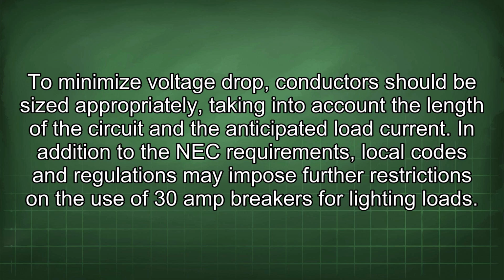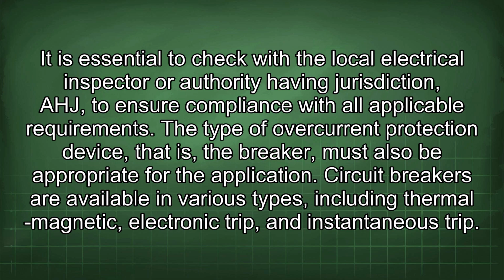In addition to the NEC requirements, local codes and regulations may impose further restrictions on the use of 30 amp breakers for lighting loads. It is essential to check with the local electrical inspector or authority having jurisdiction (AHJ) to ensure compliance with all applicable requirements.